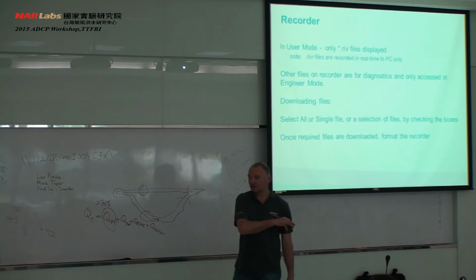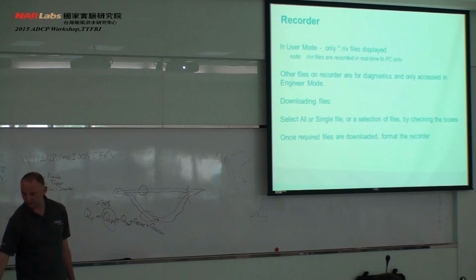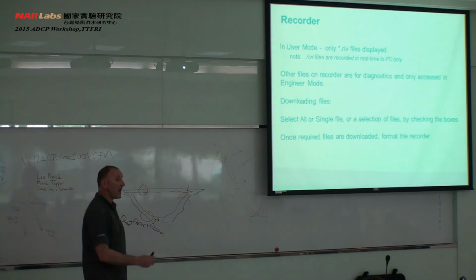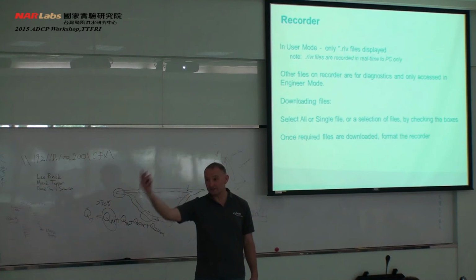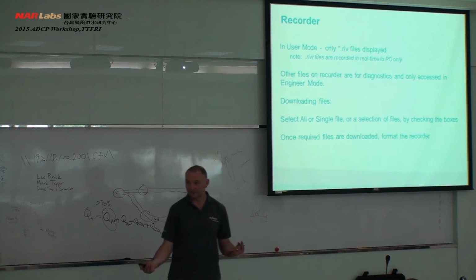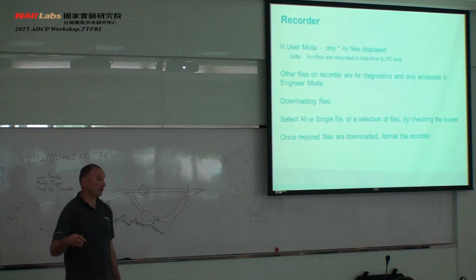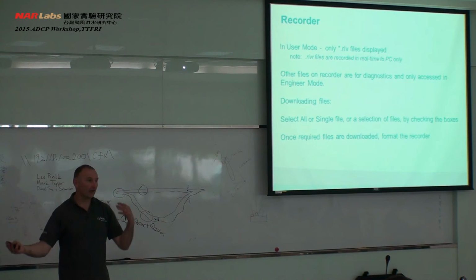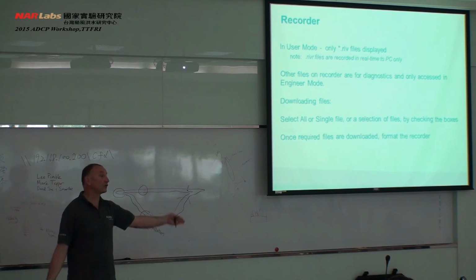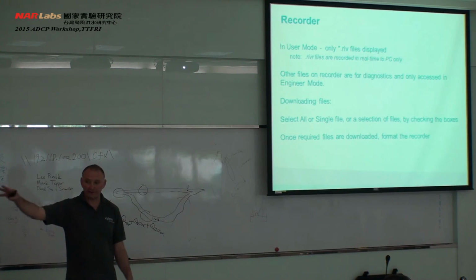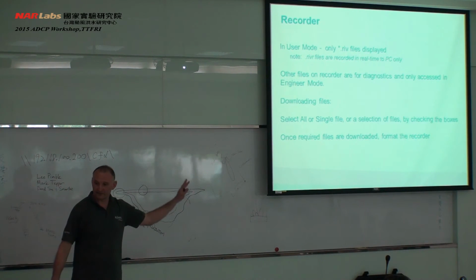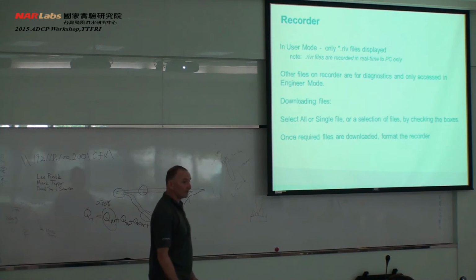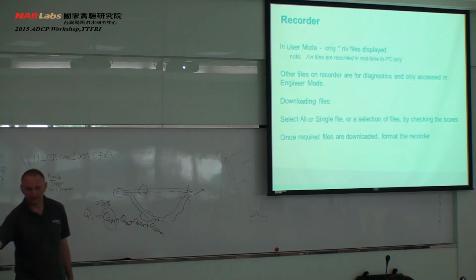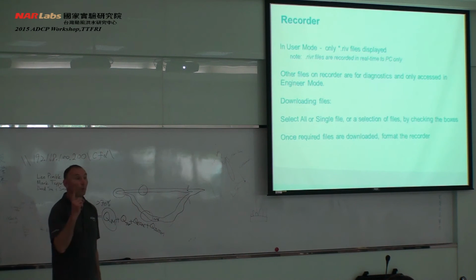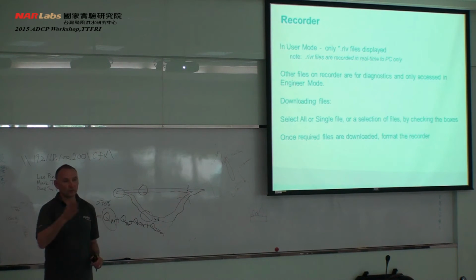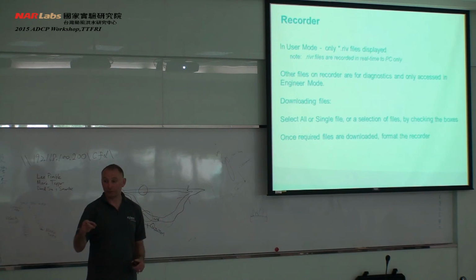The data is also being transmitted through the radio back to the PC. If you have a complete data set that has been transmitted, not 1 second of data lost, on the PC you will get a .rivr file. That is a mirror image or an exact replica of the .riv, but when we see .rivr, we know that it's a PC file. If we've got .riv, we know it's off the instrument. The third file type is if we're collecting the data with the PC and we lose 1 second's worth of data, it will label that file as missing samples.